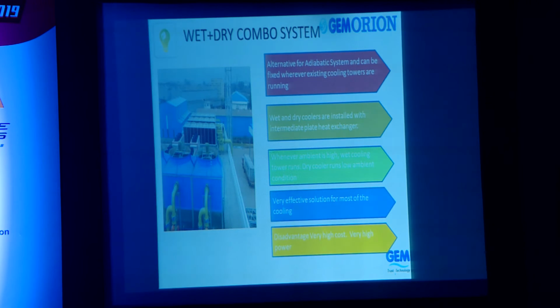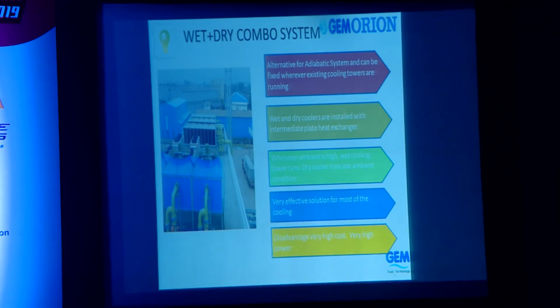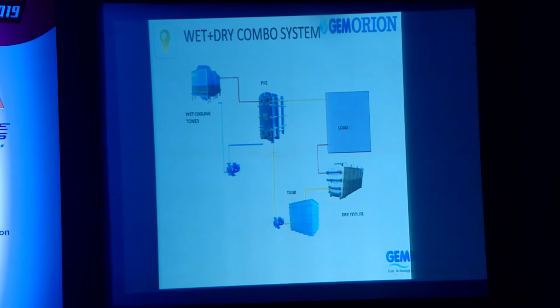So we can have a combination of wet and dry with dry or adiabatic or whatever. So this is an alternative for adiabatic. That means it is a typical combination using a plate heat exchanger and dry cooling tower with cooling tower as well. So this is very effective, and again this cost is very high. There are a lot of clients who take this concept, but they are unable to get this into this thing because of the cost. So this is the typical combination using dry cooler and the cooling tower using plate heat exchanger.